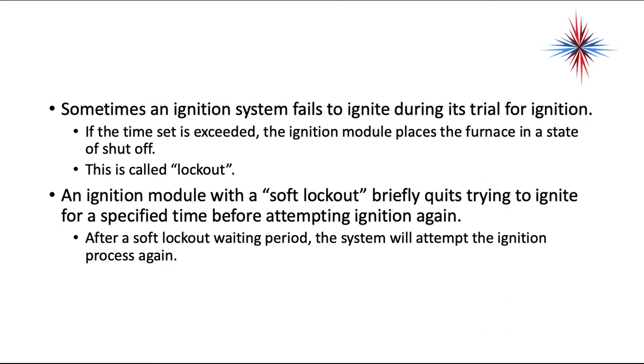Sometimes the ignition system fails to ignite during its trial for ignition. If the time set is exceeded, the ignition module places the furnace in a state of shutoff. This is called lockout. An ignition module with a soft lockout briefly quits trying to ignite for a specific time before attempting ignition again. After a soft lockout waiting period, the system will attempt the whole ignition process again, and this includes a pre-purge.